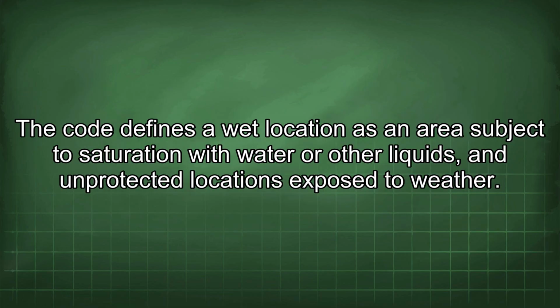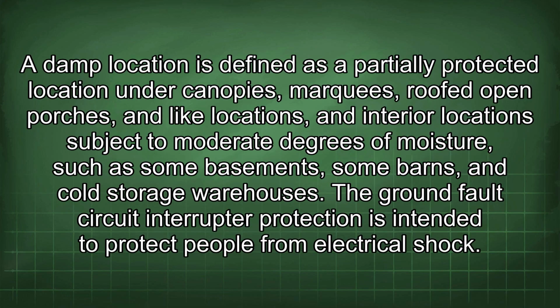The code defines a wet location as an area subject to saturation with water or other liquids, and unprotected locations exposed to weather. A damp location is defined as a partially protected location under canopies, marquees, roofed open porches, and like locations, and interior locations subject to moderate degrees of moisture, such as some basements, some barns, and cold storage warehouses.